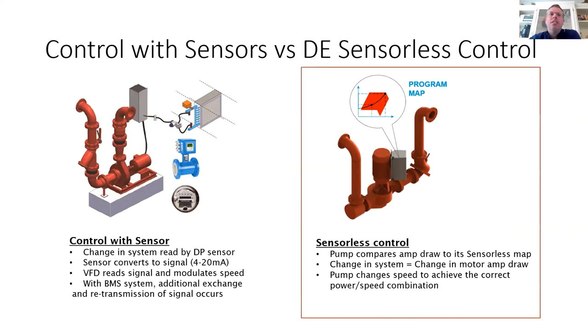In comparison, design envelope sensorless control monitors pump speed and motor amp draw, compares it to its sensorless map and control curves. As changes occur out in the system, the pump speed changes to achieve the correct power and speed combination. So the BMS system through one BACnet connection can pull in power consumption, pump speed, pump flow, pump head, status, and alarms, which can eliminate as many as four separately installed devices and takes out the guesswork as to where to install a DP sensor. So this can greatly reduce total installation costs. So if you're retrofitting an existing pumping system or designing a new pumping system, think about using Armstrong's design envelope sensorless control to help simplify things.